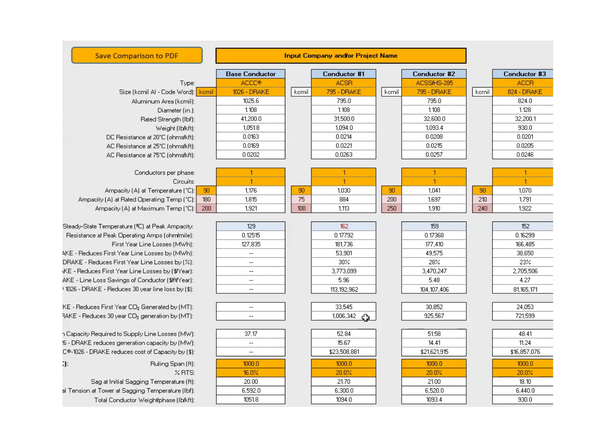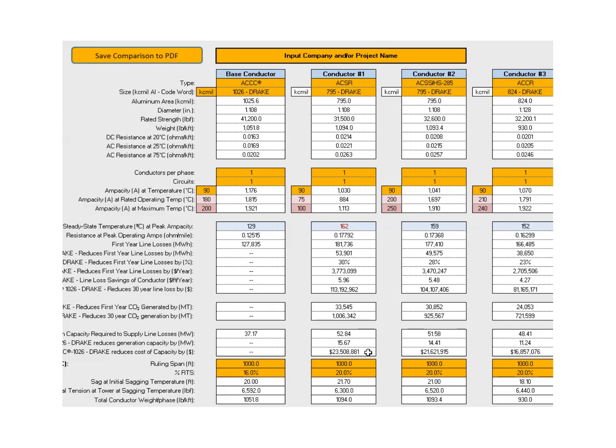Also, it's interesting that there's a tremendous amount of generation required to support line losses. By using ACCC as opposed to ACSR or ACSS, we'd be saving roughly 14 to 15 megawatts of generation in the process. Now, compared to ACSR, at $1.5 million per megawatt, that initial upfront savings would free up essentially 15.5 megawatts of generation, or $23.5 million right up front. So if you consider the cost of the conductor and the savings in generation capacity alone, this is going to pay for the conductor and installation costs with money left over to spare. We'd spend about half of that to do a reconductor project or less. So it's quite an important value proposition of ACCC, and this software program can help us easily determine that.